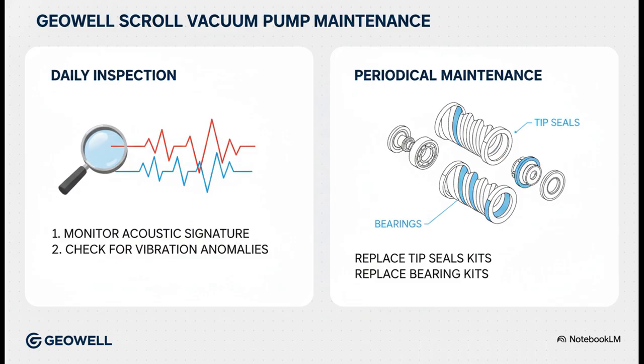Because there's no oil, the internal tip seals and bearing kits are doing all the heavy lifting, so they naturally have a prescribed life cycle. Swapping those out on schedule with Geowell's overhaul components basically resets the clock, totally restoring the pump's vacuum integrity.